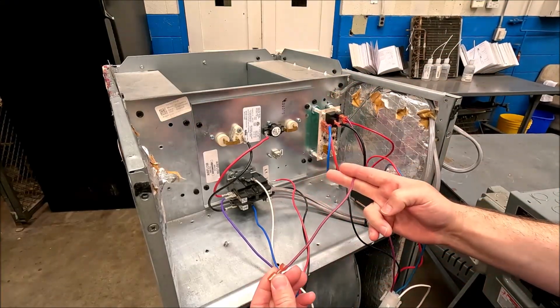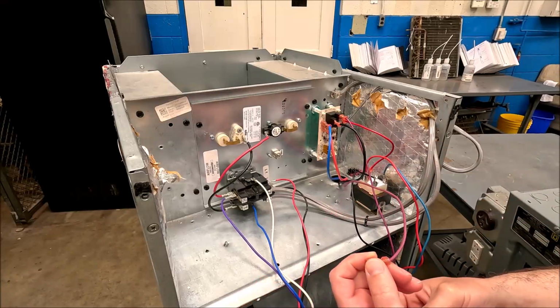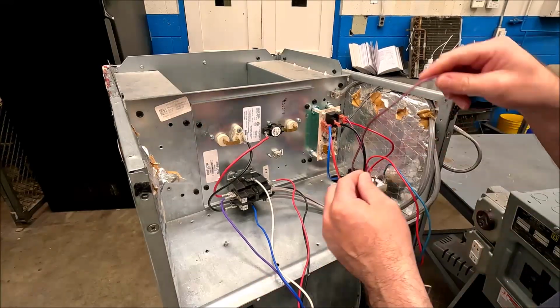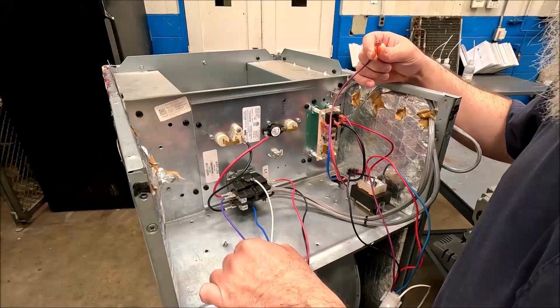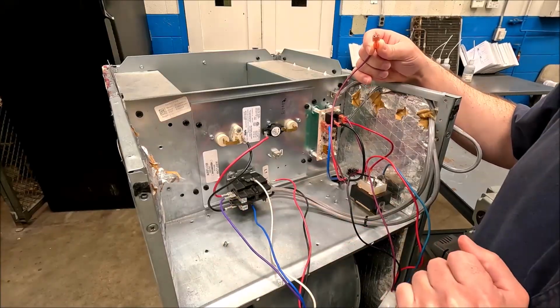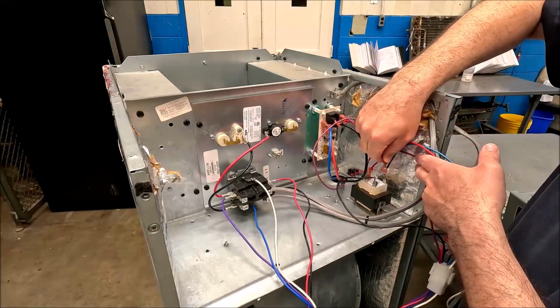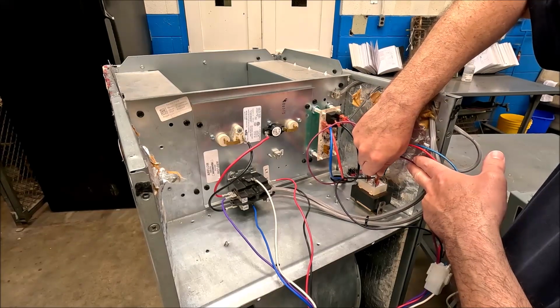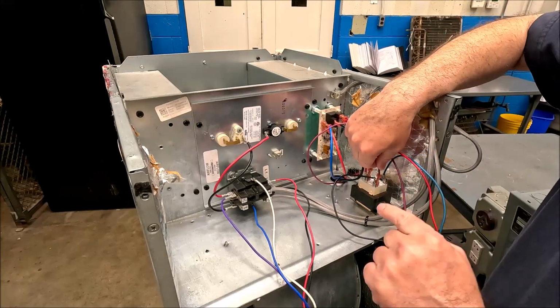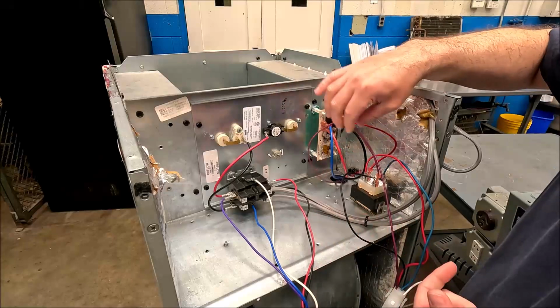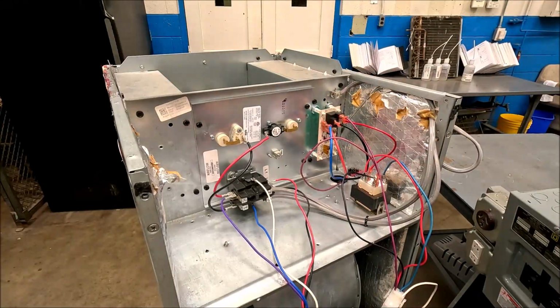And there's a purple wire coming off of the capacitor on this diagram, and it goes back. It's a purple wire, but a different purple than the heat relay purple. It goes back and jumps onto the black wire at the return side of the primary of the transformer. So that's that wire right there. And the rest are low voltage.